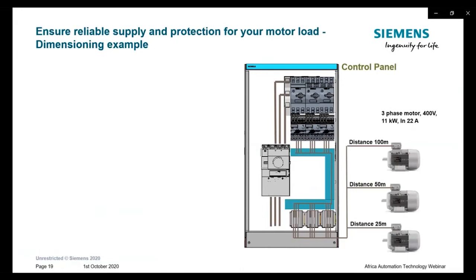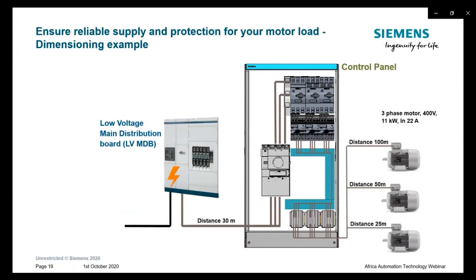So the machine control panel itself is connected to a low voltage main distribution board, and those short circuit current ratings of the electrical equipment must be determined. This can be done by means of design rules, calculation or tests, and this affects not only the main distribution board, this also affects the in-feed point of the control panel, and this affects also the motor load.